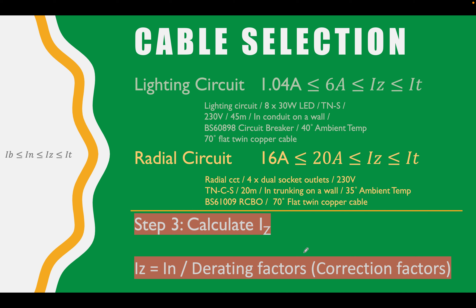When we say correction factors, what we're talking about is external influences on the current carrying capacity of the cable. For example, if we've got a cable in a loft clipped to a joist and completely covered in insulation, versus one cable clipped to a wall in a garage directly, the cable on the wall is subject to less heat. Heat creates more resistance, so if resistance is up, the current carrying capacity of the cable is going to be down.